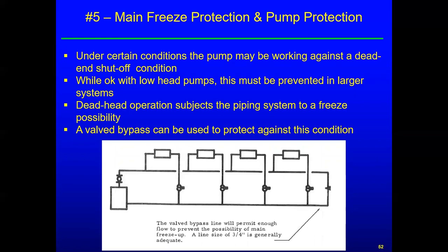Okay, so freeze protection and pump protection. It's possible, if these are two-position valves, that they could all close at one time, which would deadhead the pump. Well, that could be a problem. So sometimes you will go out at the far end of the system and put a little bypass line just to allow a flow path if perchance all of the control valves were to close at one time. Deadhead on a large pump will damage it. If it's a real small pump, it probably wouldn't hurt it much.